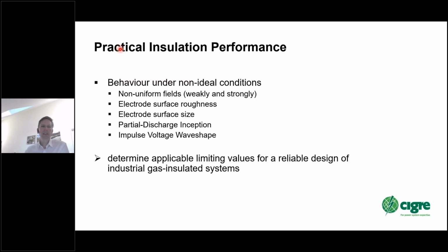One topic was to go beyond intrinsic insulation performance and look at practical insulation performance—behavior under non-ideal conditions: non-uniform fields, rough surfaces, large surfaces, partial discharge inception, and non-standard waveforms like lightning and switching impulses. From these measurements we aimed to determine limits useful for manufacturers to ensure reliable design of industrial GIS systems.